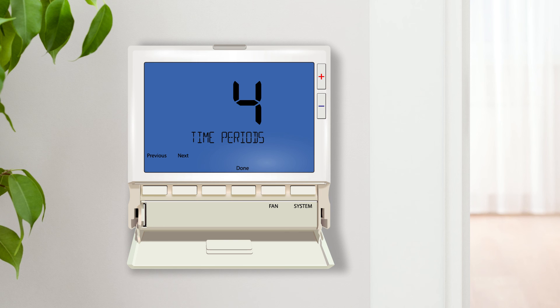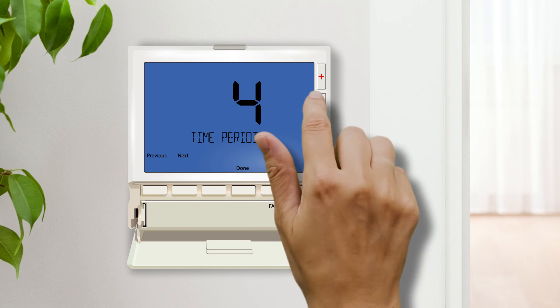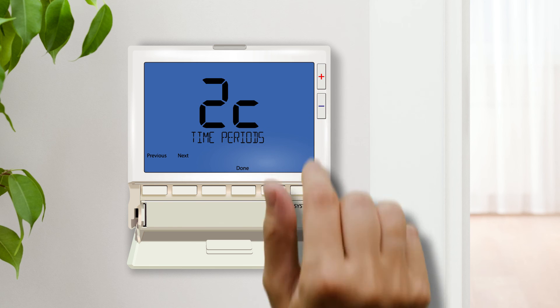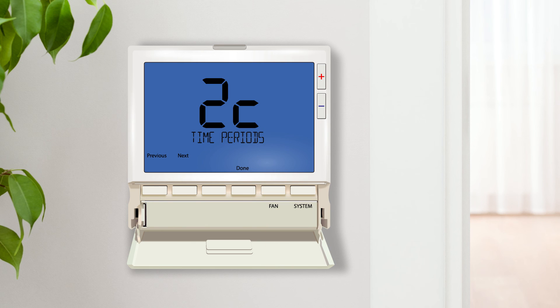The time period setting lets you select two or four time periods per day. Two time periods are most commonly used in commercial settings where the building is either occupied or empty. There is also a 4C option which allows you to select two occupied and two unoccupied time periods per day. You must choose 2C or 4C selected to set a pre-occupancy fan.